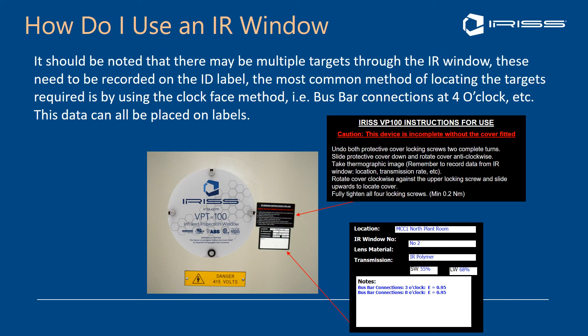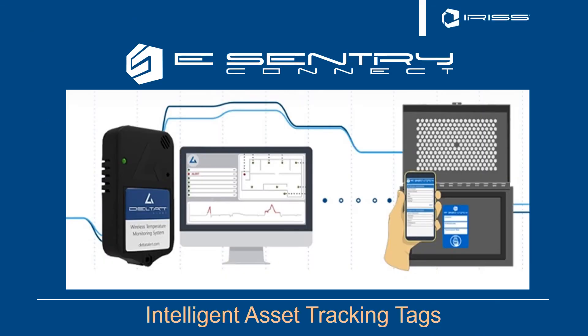Labeling is very important. We tend to use the clock face method, because you can look through one window and have multiple targets. The VPT system comes with instructions for use — put them on there because the guys using the windows may not know how to open and close them. On a written label, you can see details such as location, infrared window number, polymer material, short wave and long wave or mid-wave transmission, and target components — for example, bus bar connections at three o'clock with emissivity 0.95 and at eight o'clock with emissivity 0.95. This keeps that level of control in place.